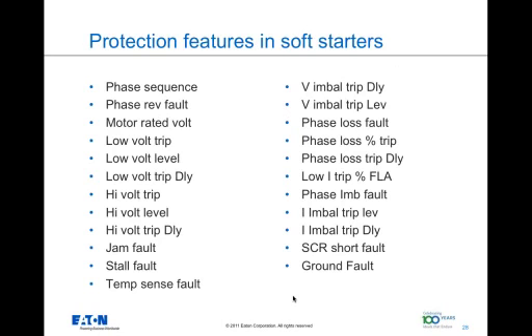So again, the intention of the slide is that modern day soft starters are not just coming with the reason they're used in the first place, which is to gradually ramp up the motor. They are coming with a lot of additional monitoring and protection functionality which can help the customer do away with some of the traditional ways of measuring and monitoring various things in the system. And that would tremendously reduce the cost of switching over from a traditional way of starting the motor to a soft starter.